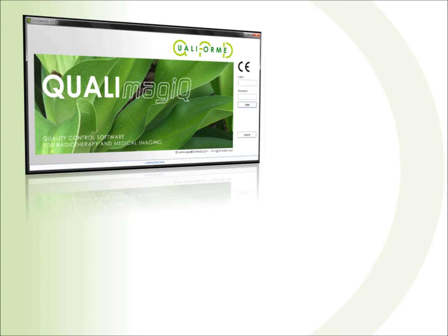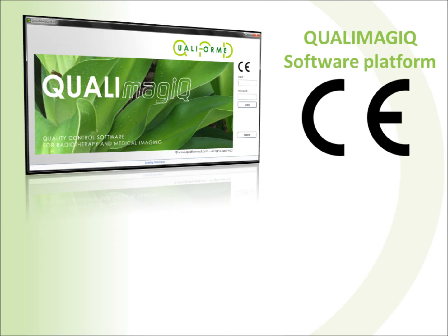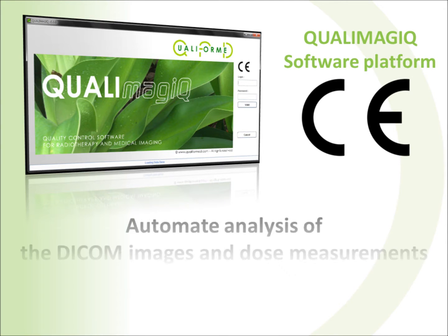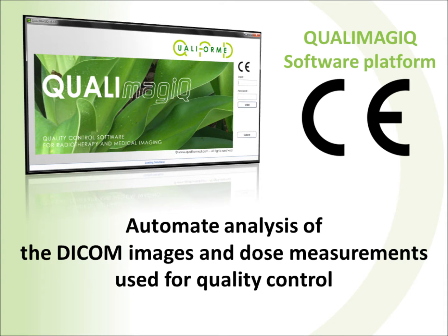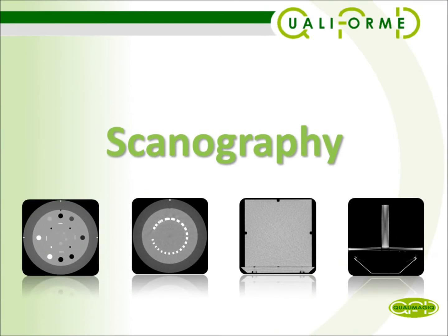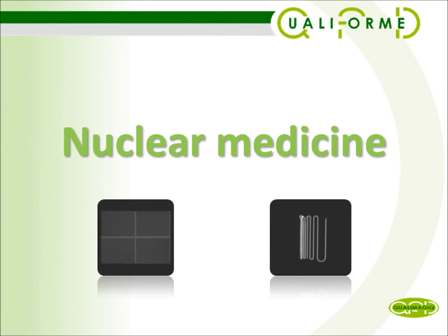QualiMagiQ is a CE-certified software platform published by the French firm QualiFormeD. It enables you to automate analysis of the DICOM images and dose measurements used for quality control of your radiotherapy, scanography, MRI, and nuclear medicine machines. QualiMagiQ also automates traceability of your quality control analyses.